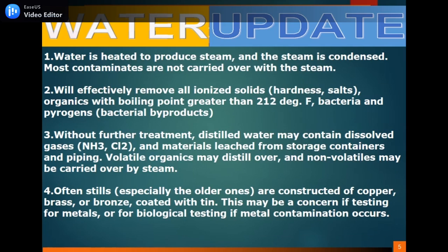In distillation, water is heated to produce steam and the steam is condensed. Most contaminants are not carried over with the steam. This will effectively remove all ionized solids, hardness salts, organics with a boiling point greater than 212 degrees Fahrenheit, bacteria, and pyrogens. Without further treatment, distilled water may still contain dissolved gases, ammonia, chlorine, and materials leached from storage containers and piping. Volatile organics may distill over and non-volatiles may be carried over by steam.